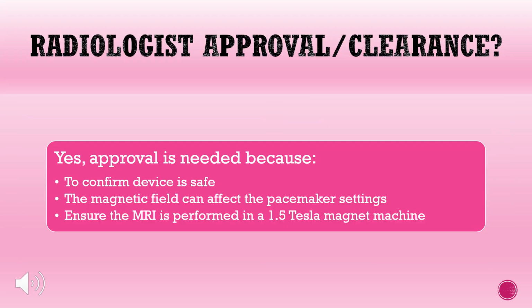Radiologist approval and clearance is needed for patients with a pacemaker because they can confirm that the device is safe. They know that the magnetic field can affect the pacemaker settings, so they will have to agree that the MRI exam is still the best option for the patient. And the radiologist will want to ensure that the MRI is performed in a 1.5 Tesla magnet machine.